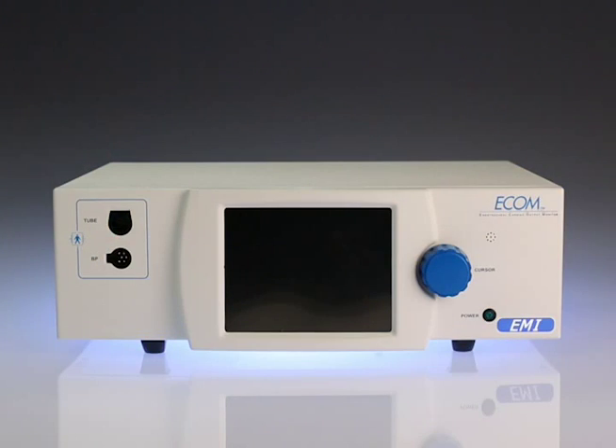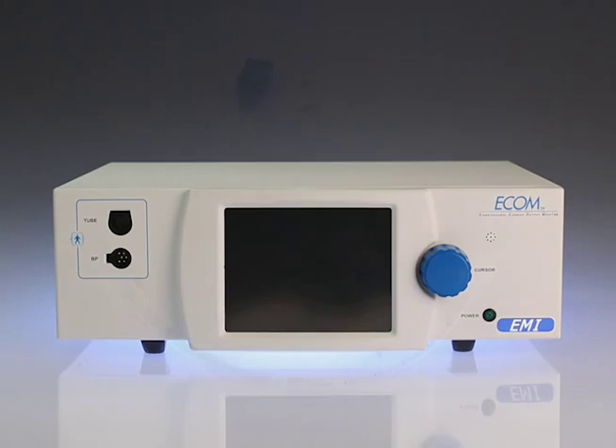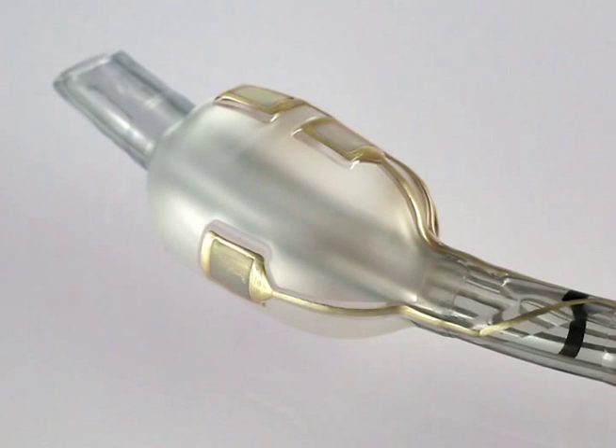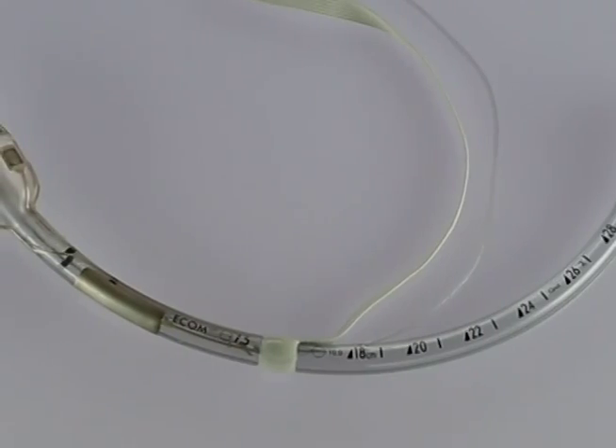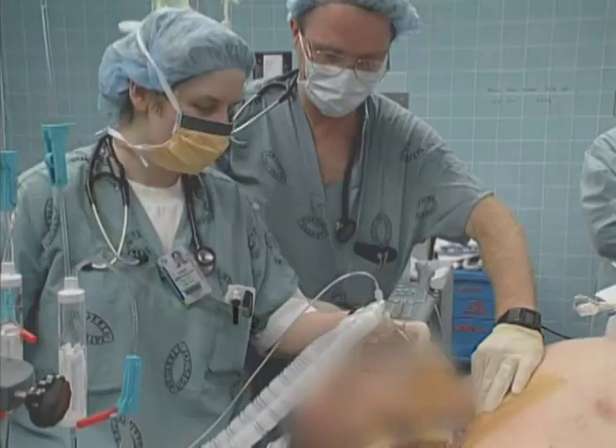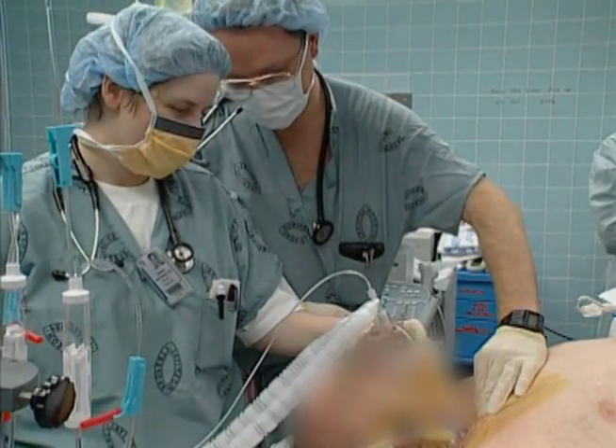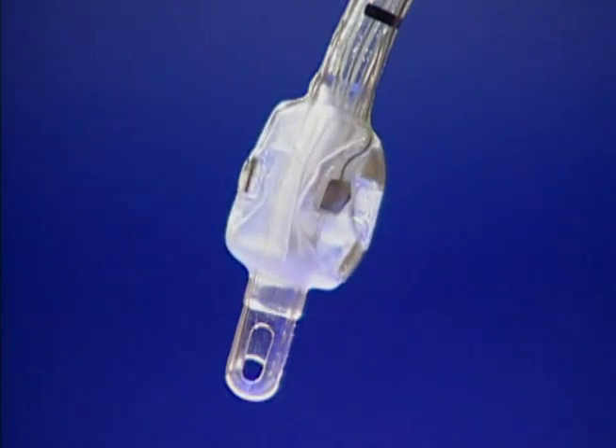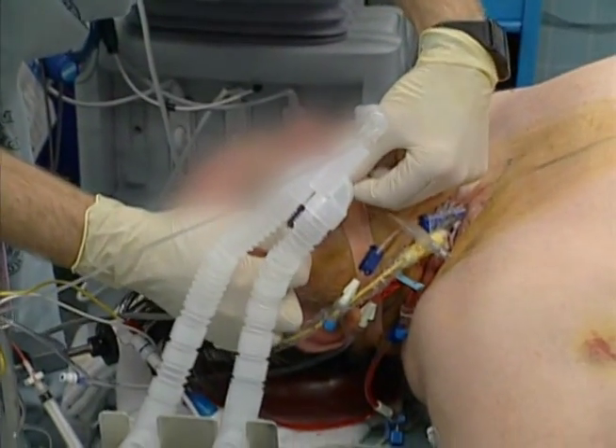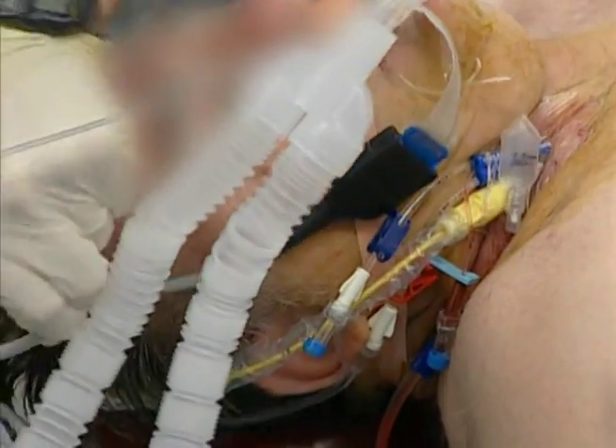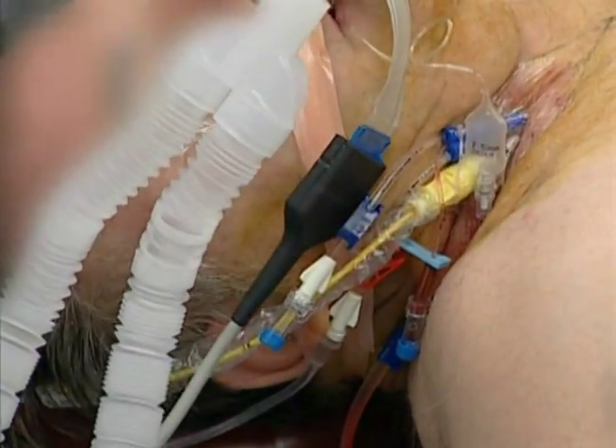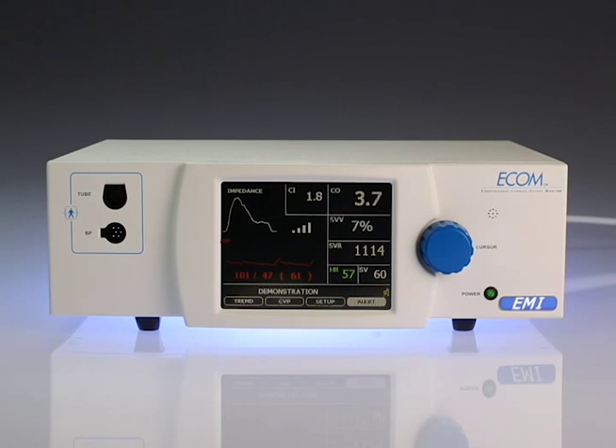The ECOM system consists of a monitor, cable, and endotracheal tube with 6 electrodes on the cuff and a source electrode on the shaft. The endotracheal tube is inserted using standard technique. Once the cuff is inflated, the tube cable is connected to the monitor and real-time continuous cardiac output, as well as other hemodynamic parameters, are displayed. The following animation demonstrates the use of the ECOM system and the principles of impedance cardiography.